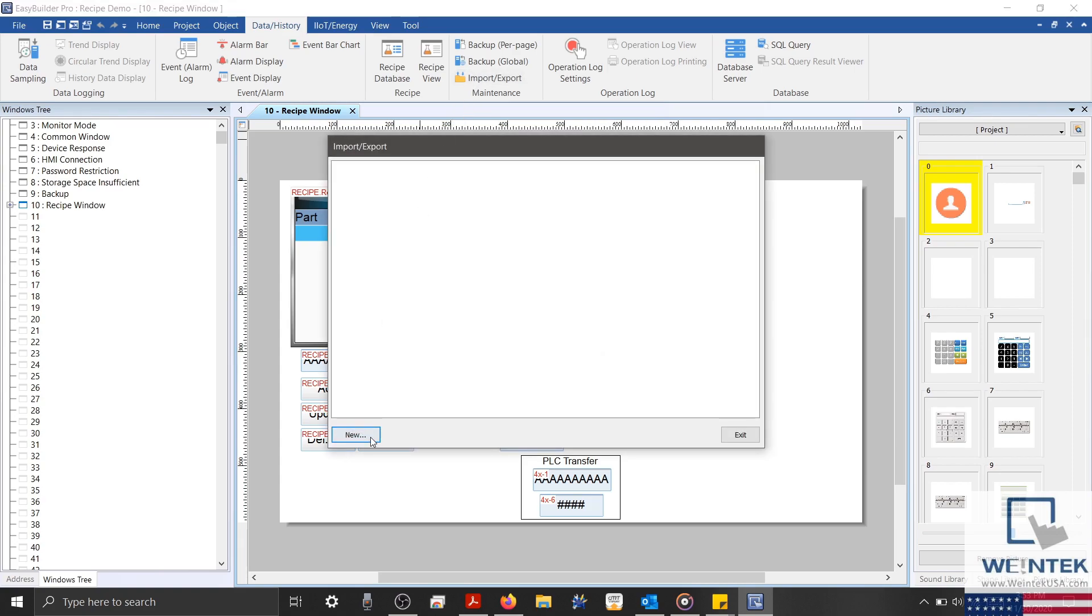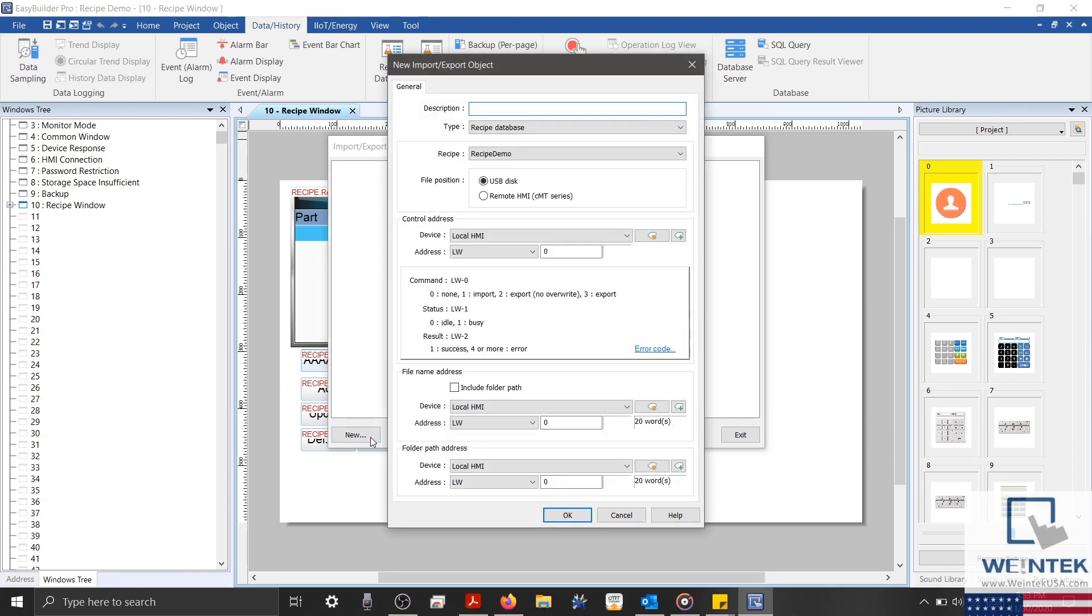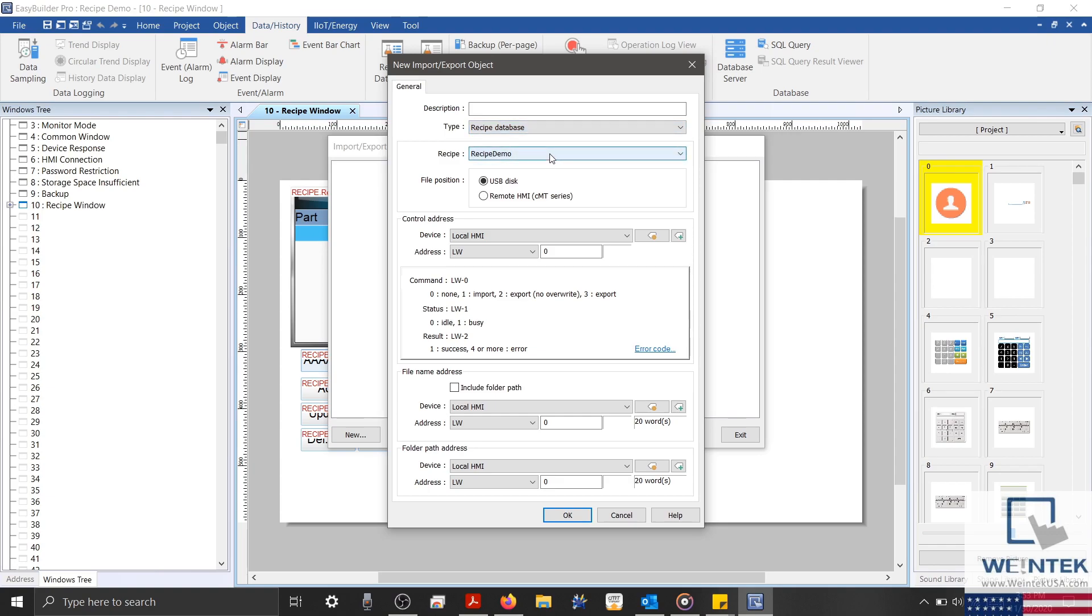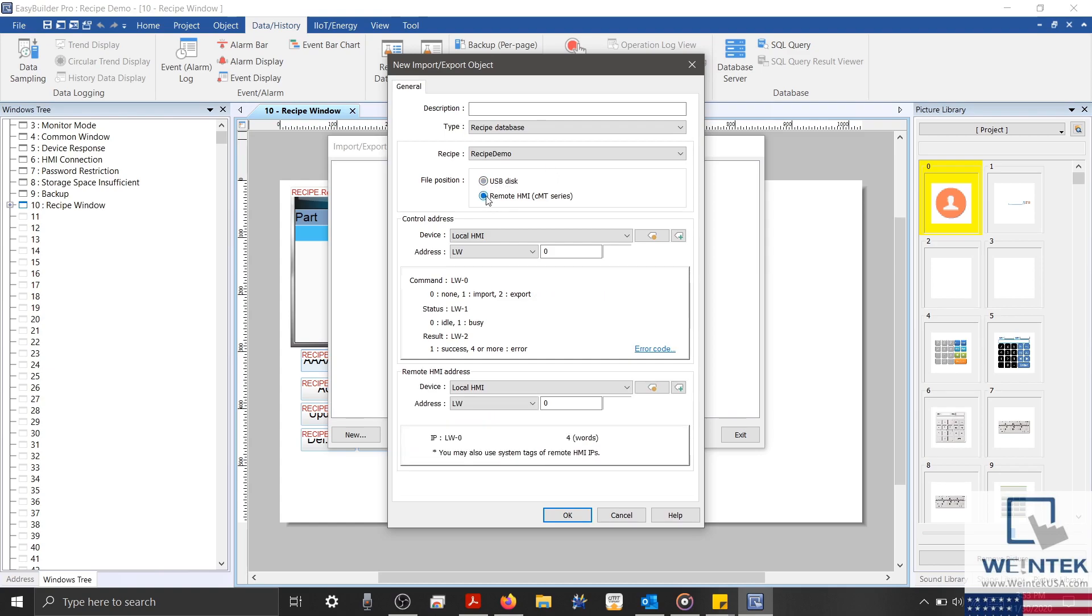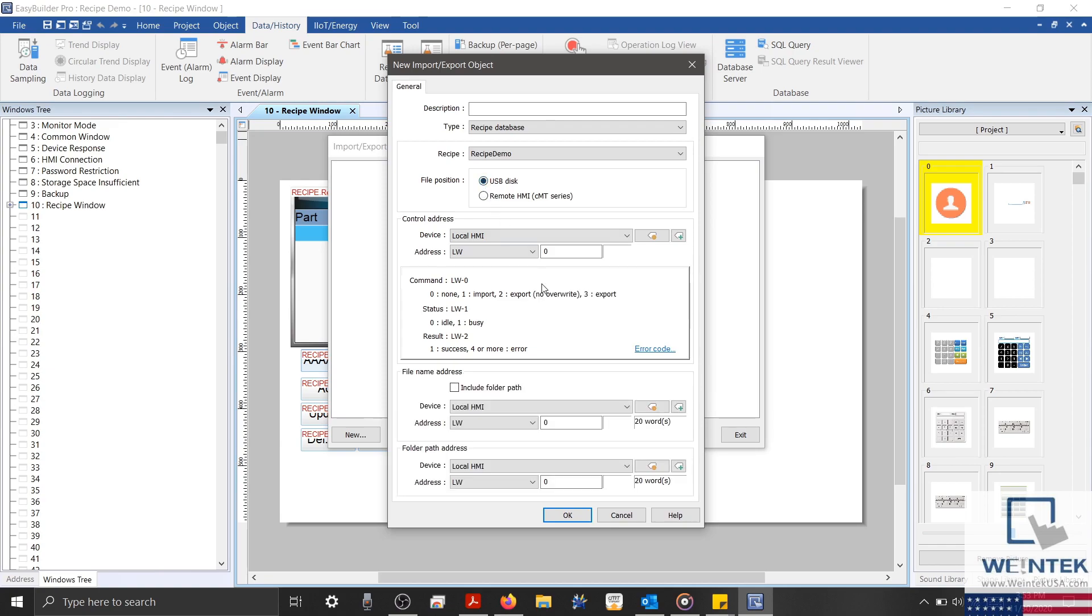And when prompted, I'll select new to create a new object. I'll ensure recipe database is selected within the type dropdown list. Then within the recipe dropdown list, we'll select the recipe that we want to export. When exporting recipes, I can either send this recipe to a remote HMI, or save this within a USB disk. During this demonstration, we'll make sure that USB disk is selected.